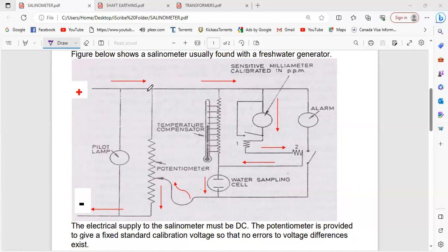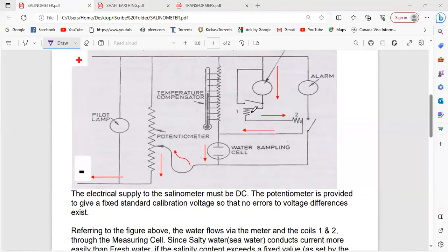And by increasing current in the system, it will correspondingly activate these current operated relays. They are not voltage operated relays. You can see that straight away from the simple fact that they are in series. If they are in series, they are current operated relays. So because of the increased current flow, the respective relays 1 and 2 are going to get energized. Number 2 giving the alarm, and number 1, which is going to short out the display.